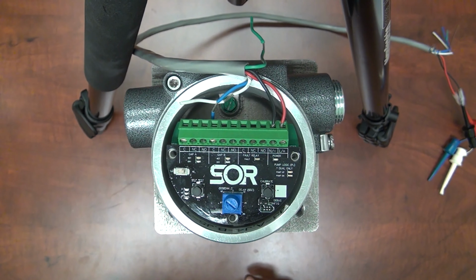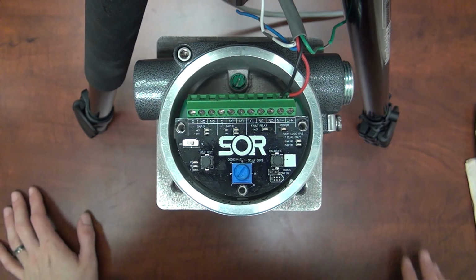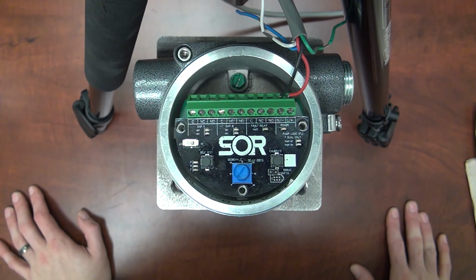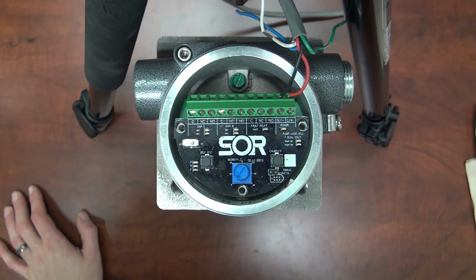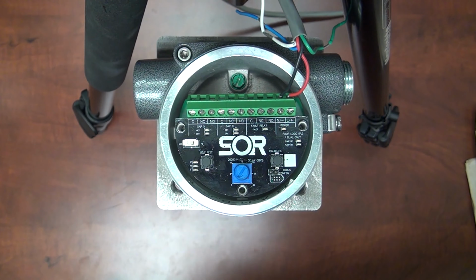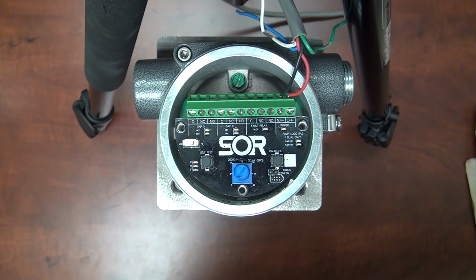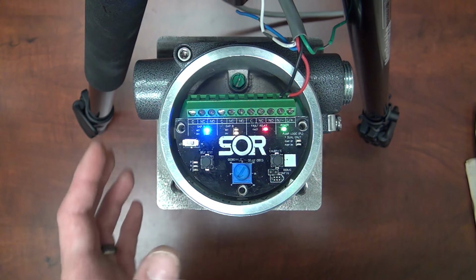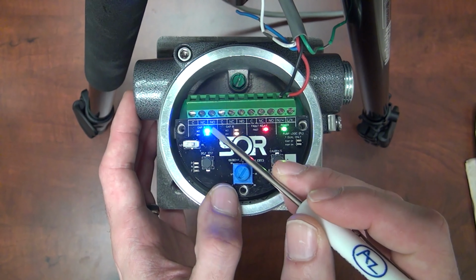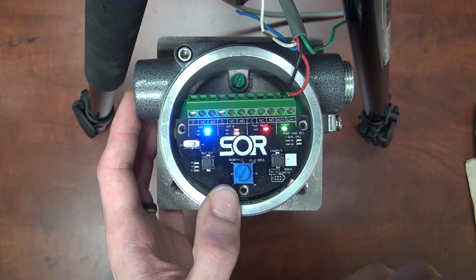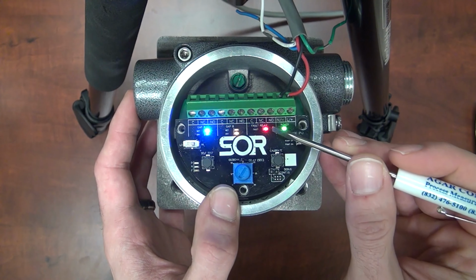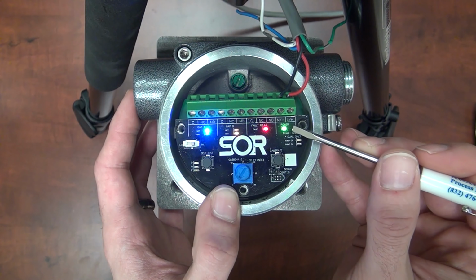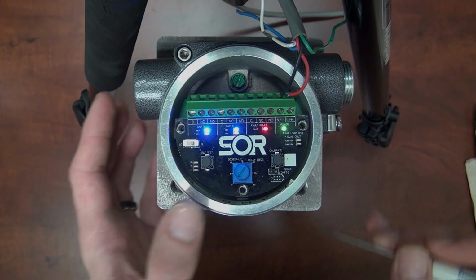First, we're going to start with the sensorless calibration. Now, let's take a look at what the device will indicate when a sensorless calibration is required. When we turn on power to the device, the LEDs will begin flashing to indicate the fault that is occurring. Here we see both the gap A and gap B, wet and dry LEDs flashing repeatedly, with the fault relay LED on and the power relay LED on.